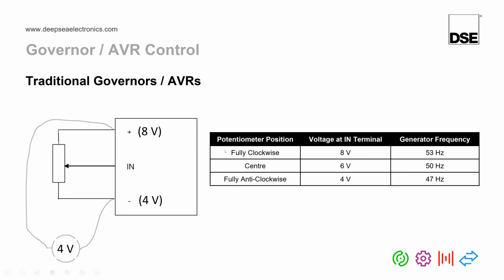It's also worthwhile noting that I have just used some typical labeling here as plus, in, and minus, but there's no standard for this on different governors or AVRs. You might find it labeled as ABC, T1, T2, T3, XYZ. It could be anything, but normally you'll be able to find this out by looking at the governor or AVR manufacturer's literature, and normally the typical wiring diagram will give you some idea about that.